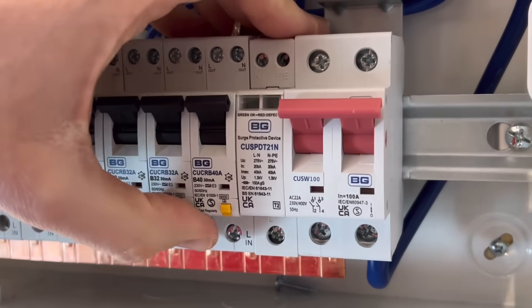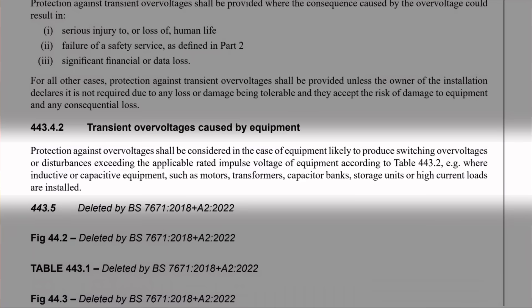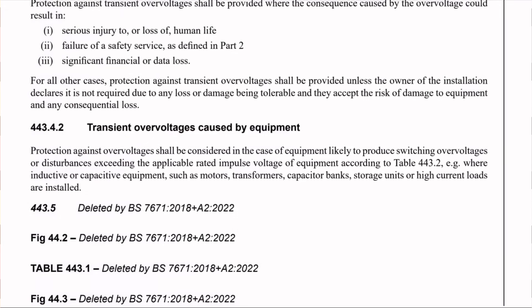The other requirement in this section on overvoltage is regulation 443.4.2, with the heading 'transient overvoltages caused by equipment'. This paragraph relates to surges in voltage that can be caused by machinery switching on and off, usually ones that are inductive or capacitive in their nature - like motors, transformers, and capacitor banks - or loads that draw a lot of current. Interestingly, this regulation starts by saying that protection against this kind of overvoltage 'shall be considered' - it doesn't say 'installed'. So this regulation is a little less forthright than the one just before it.